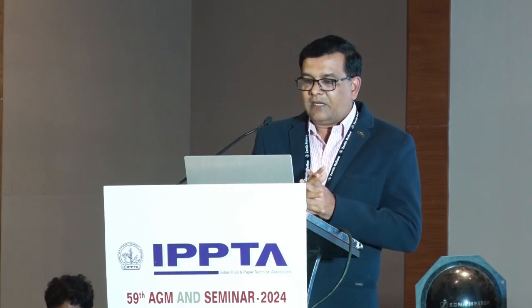Then we had a moving bed biological reactor in our ETP, for which there were low-pressure blowers. Blower 1 and blower 2 were running when we installed the plant. The Nm cube was 4200 and 4550. We replaced them with centrifugal air foil bearing type blowers, with non-contact bearings for the shaft. It is a Sulzer blower. For 8000 Nm cube, it takes only 186 kilowatt. So we invested around 65 lakhs and the payback was 1.35 years. The saving was 109 kilowatt and the equivalent CO2 is 1443 tons.